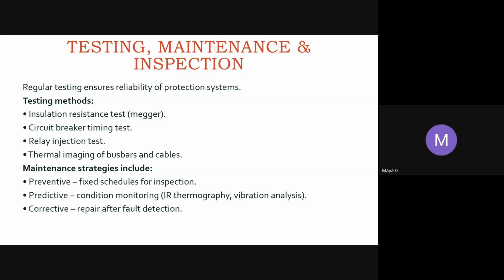Maintenance strategies include preventive, predictive, and corrective maintenance. Preventive: at fixed intervals, we schedule the inspection of each and every point. Predictive: by using thermography, we can identify whether there is any chance for an arc to occur. By using vibration analysis also, we can identify hazardous conditions. By monitoring all these things, we can predict whether there is a possibility of any accident. And corrective: after a fault or accident occurs, we have to repair our equipment associated with the arcs and take corrective actions.